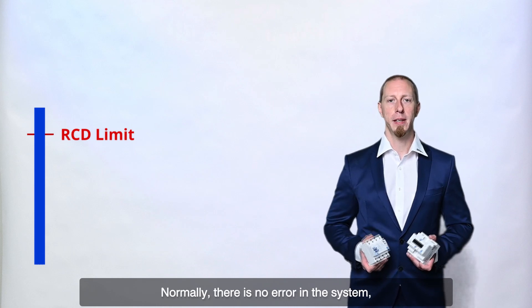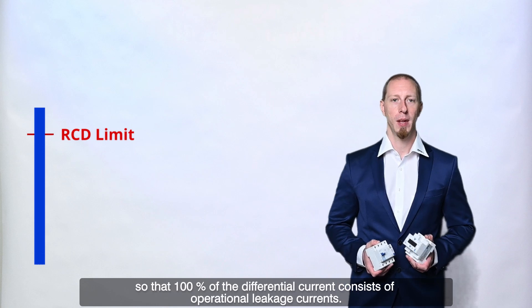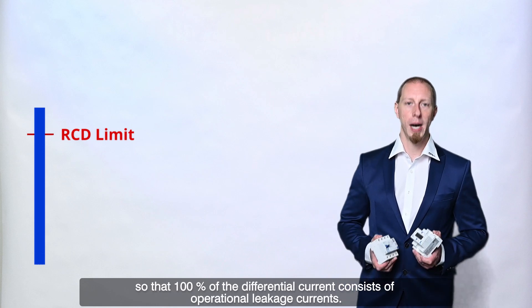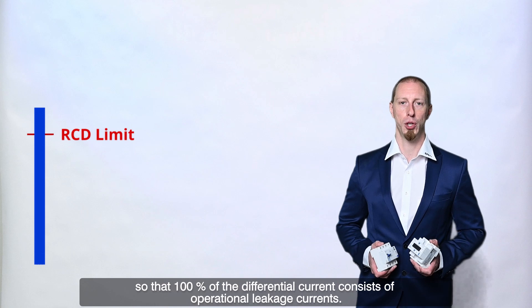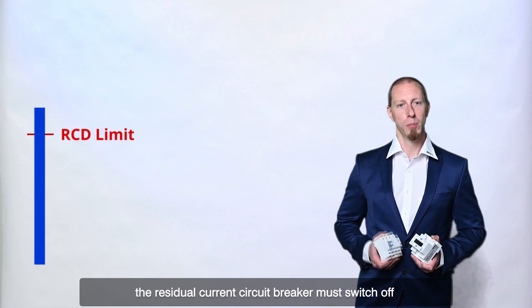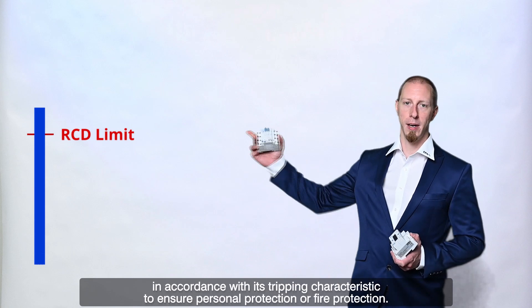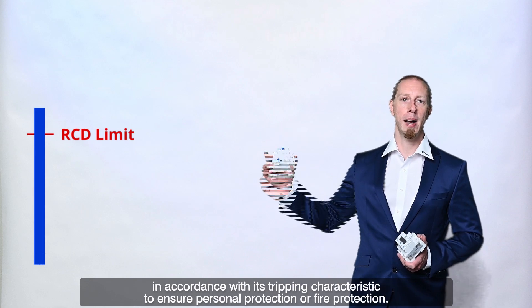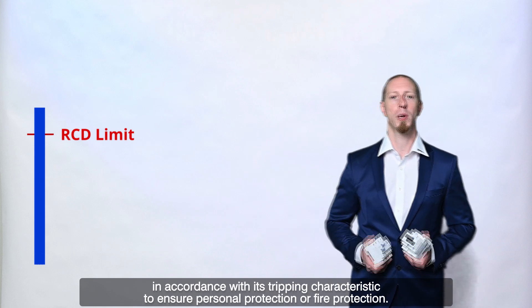Normally, there is no error in the system. So that 100% of the differential current consists of operational leakage currents. If these currents reach a certain level, the residual current circuit breaker must switch off in accordance with its tripping characteristic to ensure personal protection or fire protection.